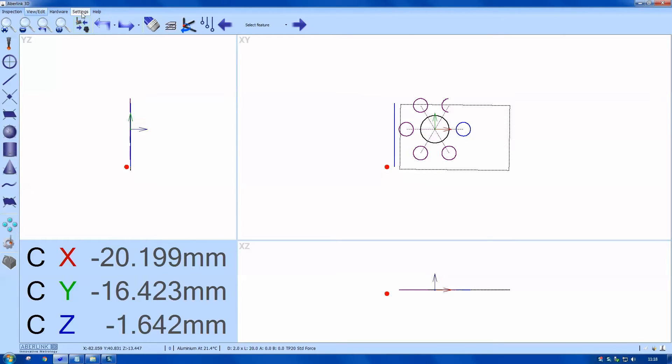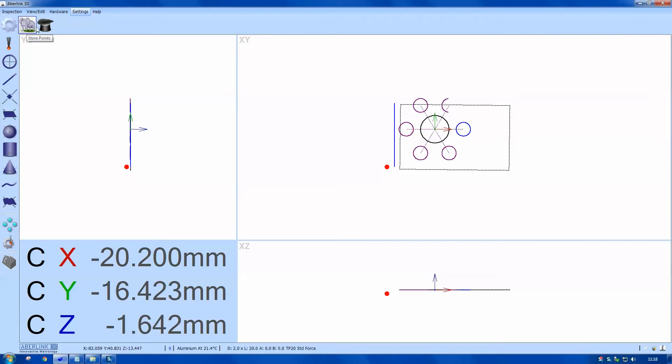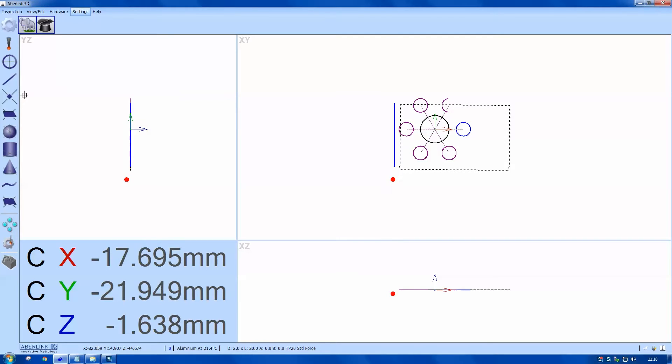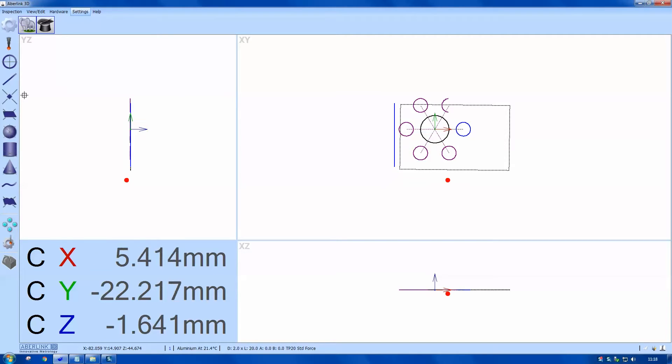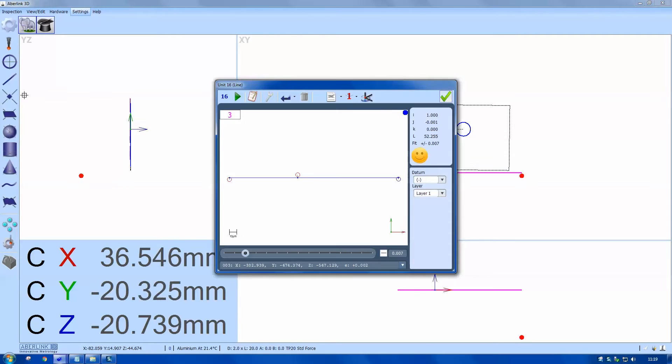Right. I'm going to use a feature predict mode. So this is a memory button. I want the memory on and the wand across the top hat which means feature predict is active. So I don't need to choose a feature. I just need to measure either a line, circle or a plane. So I'm just going to measure the front edge as a line. This appears on the third point.